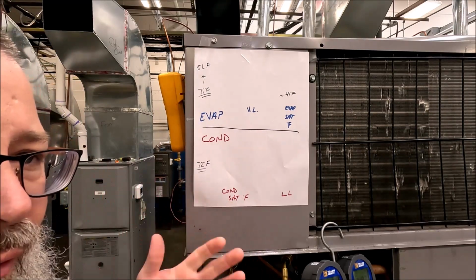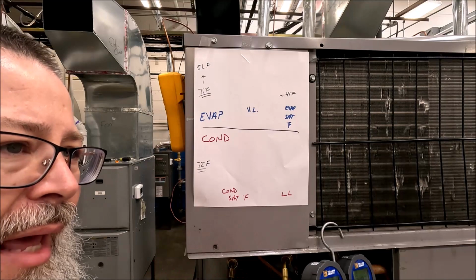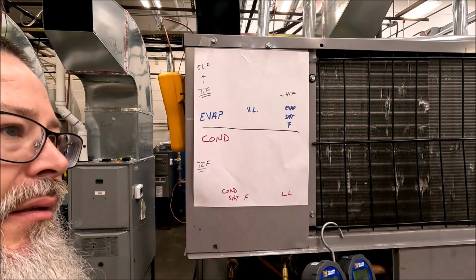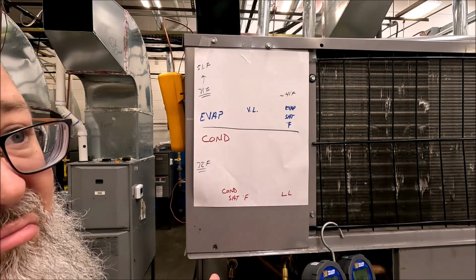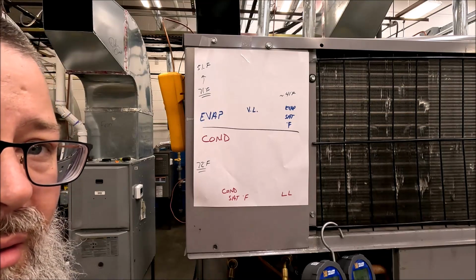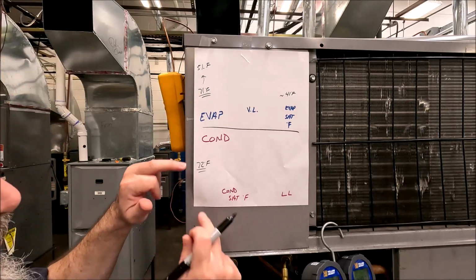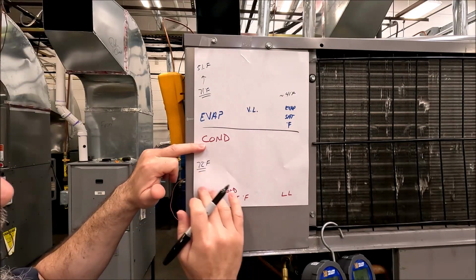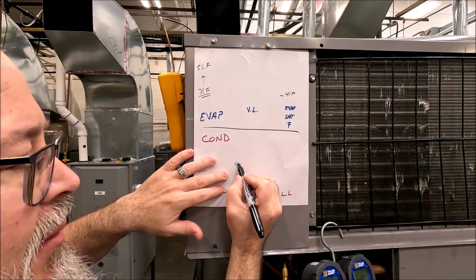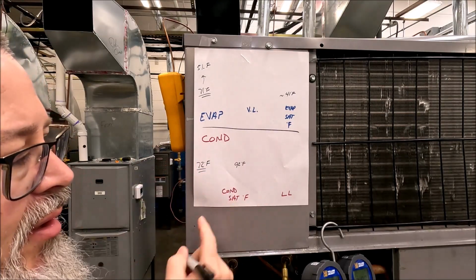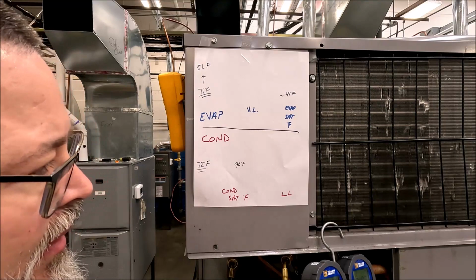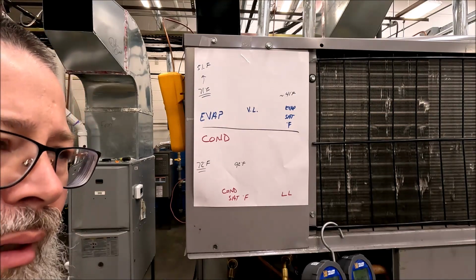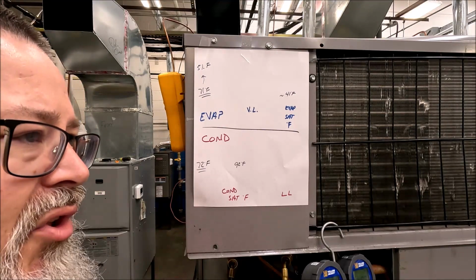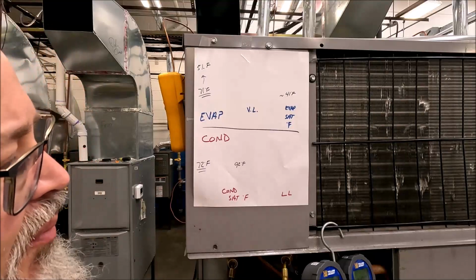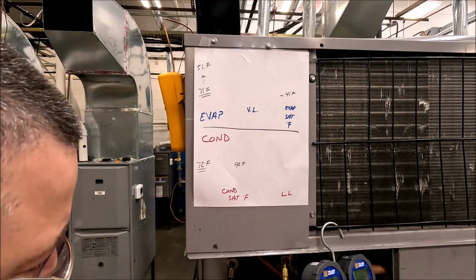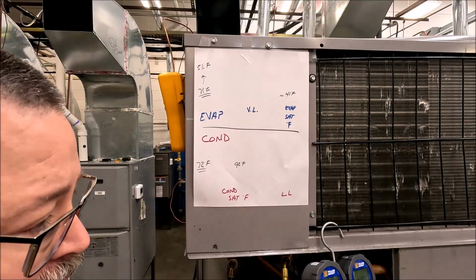With the 14, 15 SEER, we're gonna add about, let's see, what are we talking about? 15 to 20 degrees? So if I worked in that range, I would expect on a high end maybe 92 degrees for my saturation temperature, just as a starting point. Of course, this is all just a rule of thumb, giving you something to put in your mind. So let's look at it real quick.